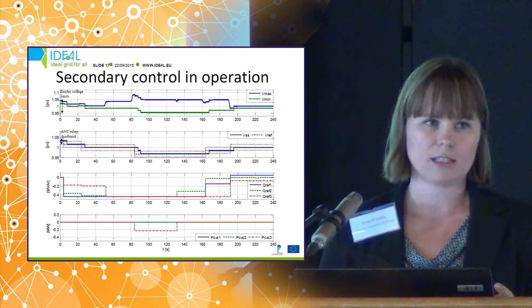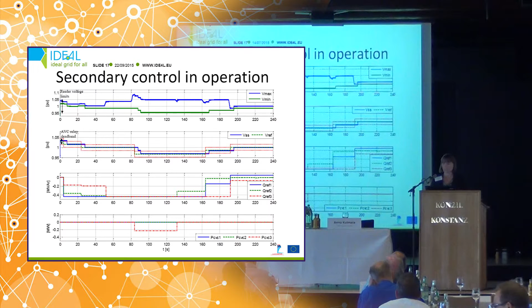We could also utilize the secondary voltage control. As you can see in the uppermost figure, it is able to restore the voltages always between the voltage limits that are set in this example case at plus minus 5%. And it utilizes the transformer tap changer and the real and reactive powers of the DG units to do this. The change in curtailed generation is quite large. This figure has been done by calculating the load flows throughout the whole year, and if we use the currently used unit power factor control algorithm, we will end up curtailing almost half of the generation in this example case. With the secondary control, we curtail 2%. So the change is quite large.